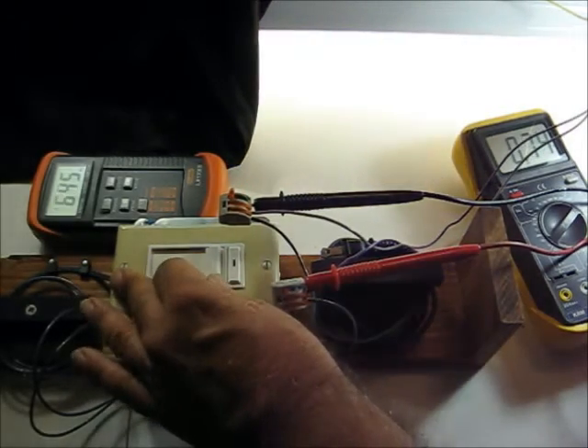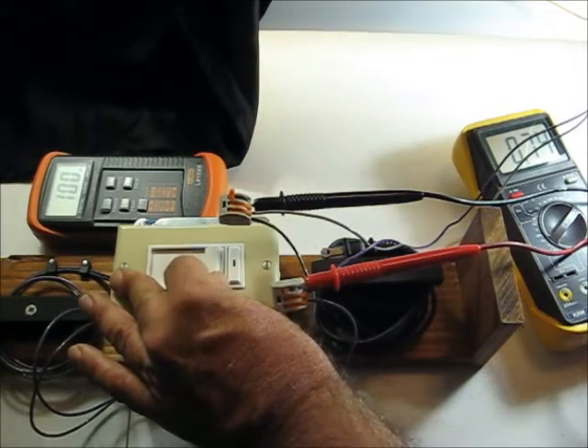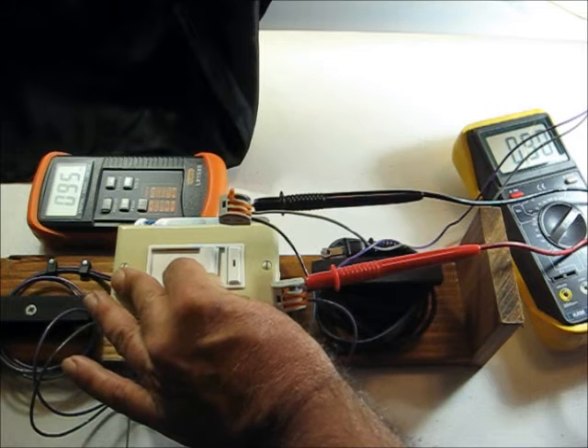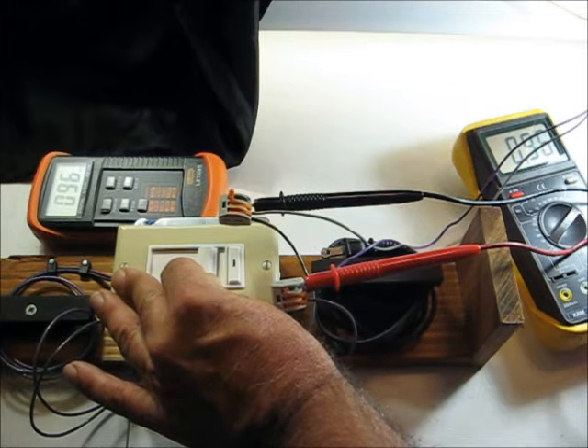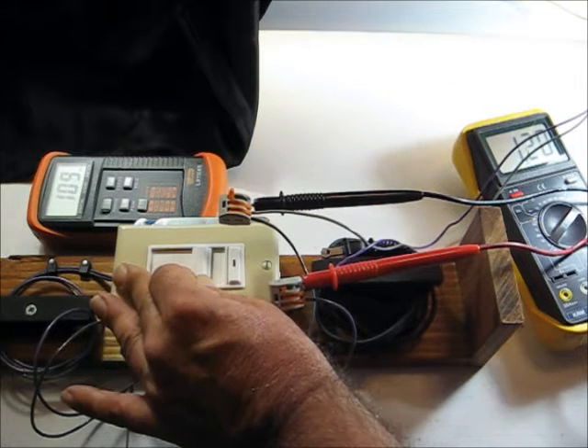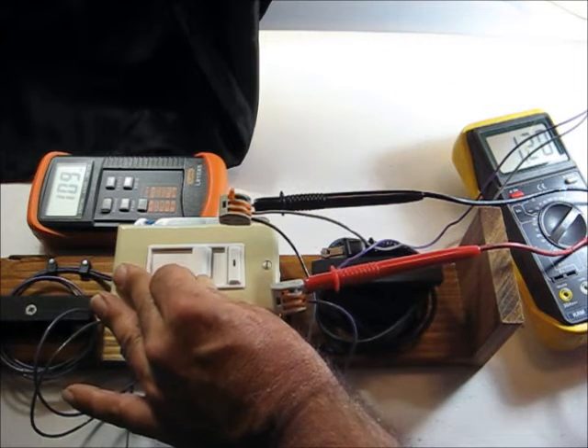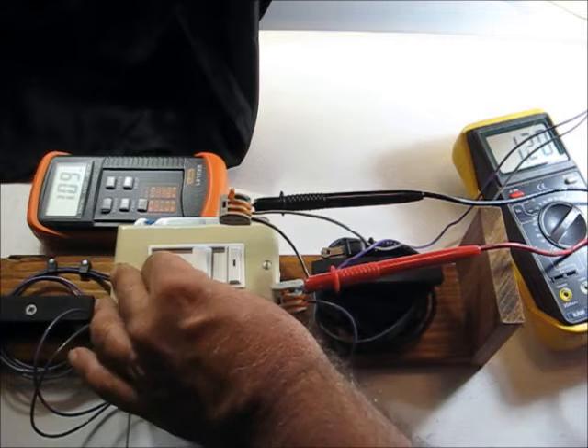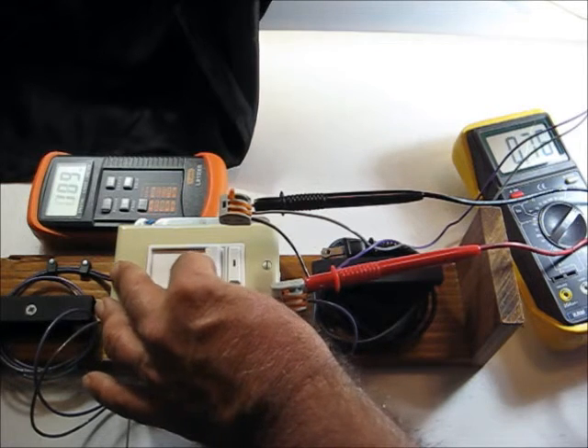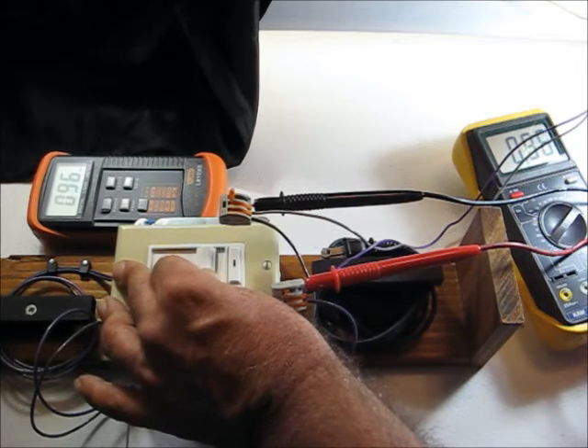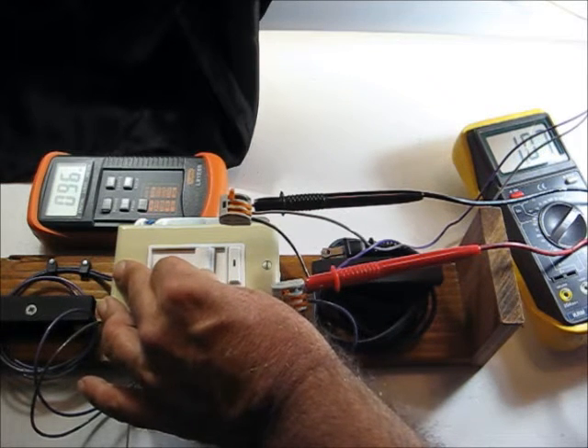Then we're going to want to find the bottom end on it, which is the bottom of the dimming range. And I'm finding it to be about 1.2 volts. Right, bottom of the dimming range.